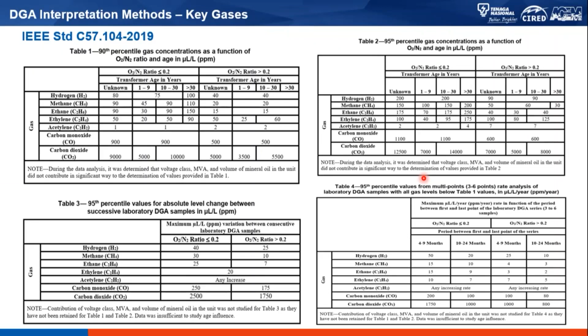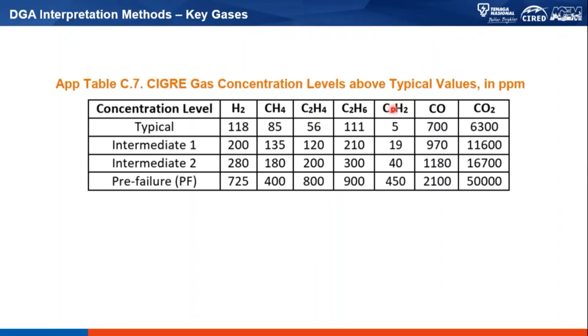Okay, so this is the key gases technique. There's another method issued by CIGRE called table C7. This is a guideline by CIGRE on the typical, intermediate number 1, intermediate number 2, and pre-failure limits of these key gases. These gases are hydrogen, methane, ethylene, ethane, acetylene, carbon monoxide, and also carbon dioxide.